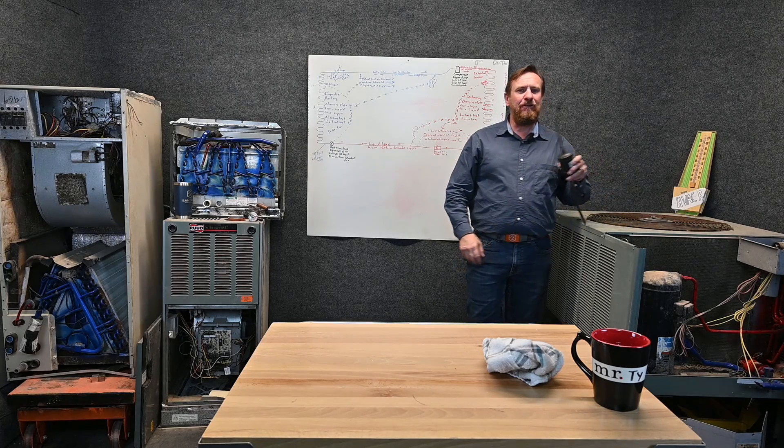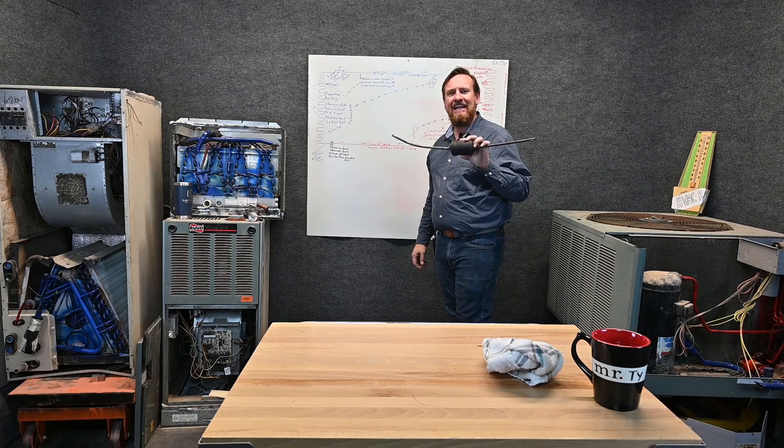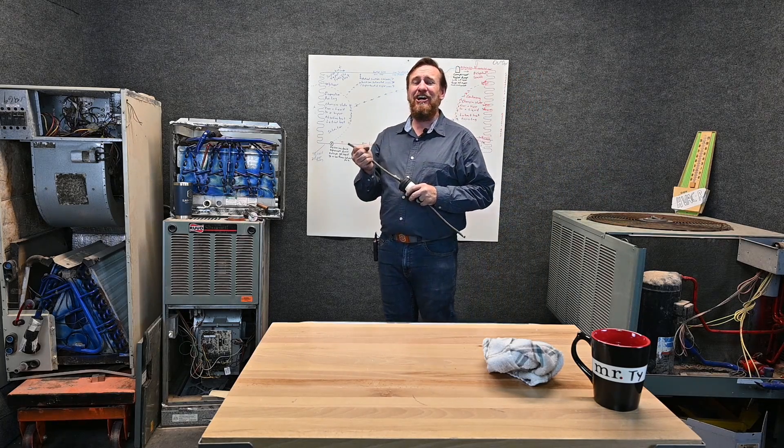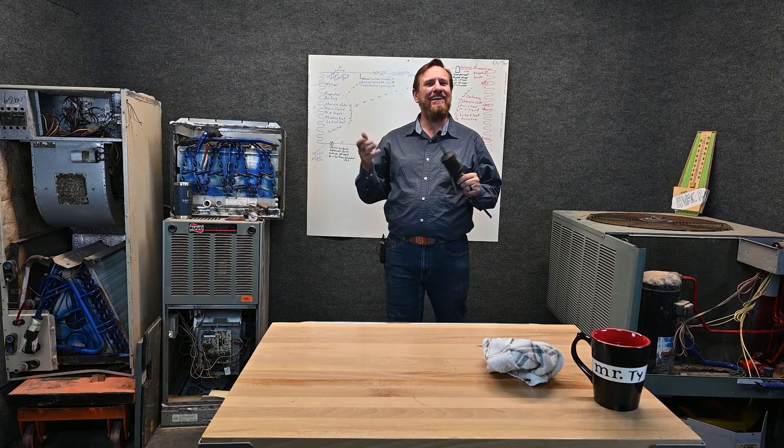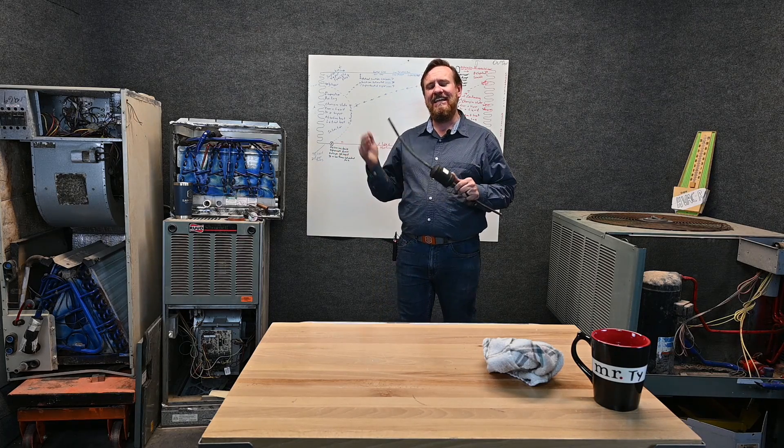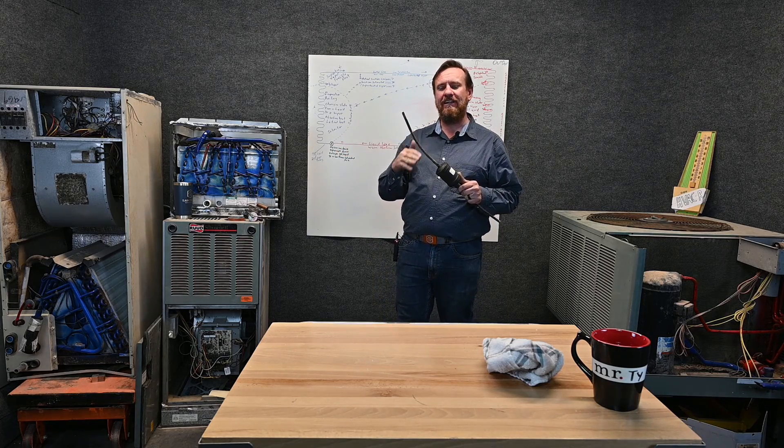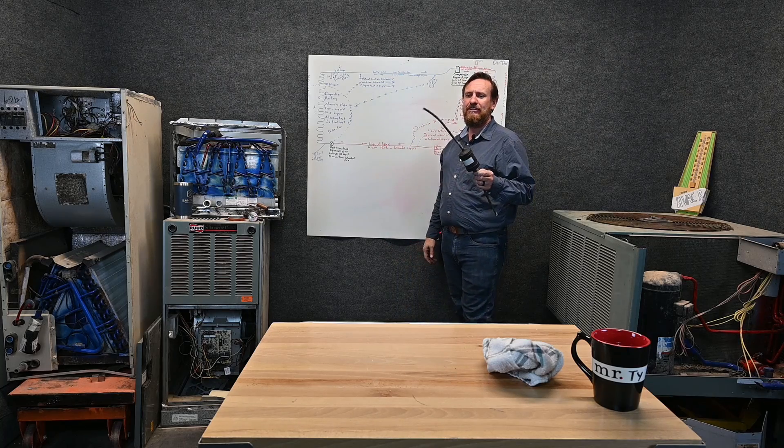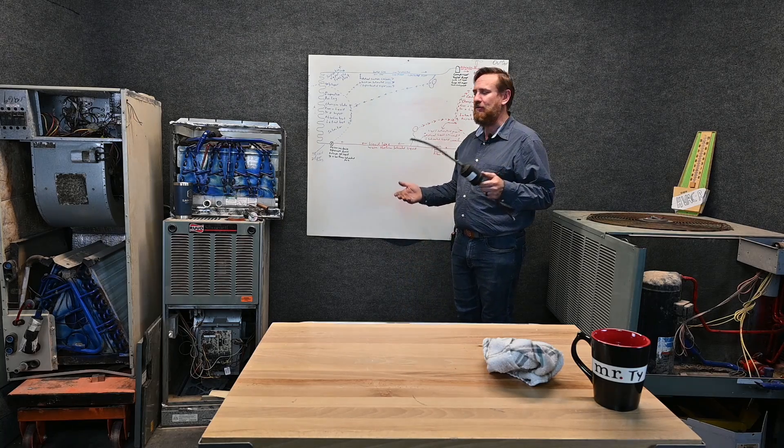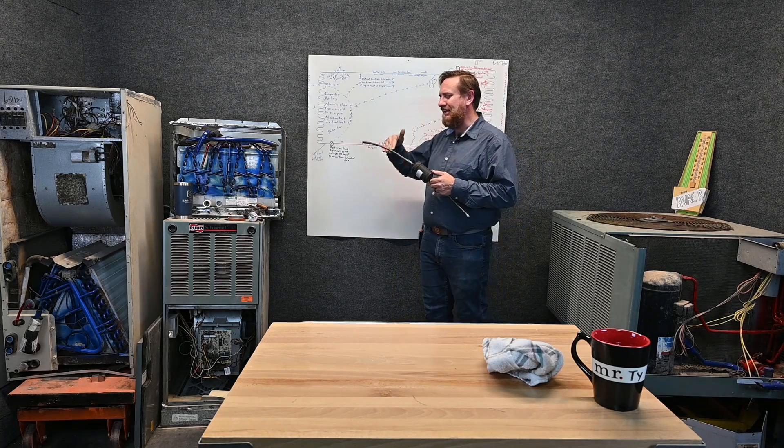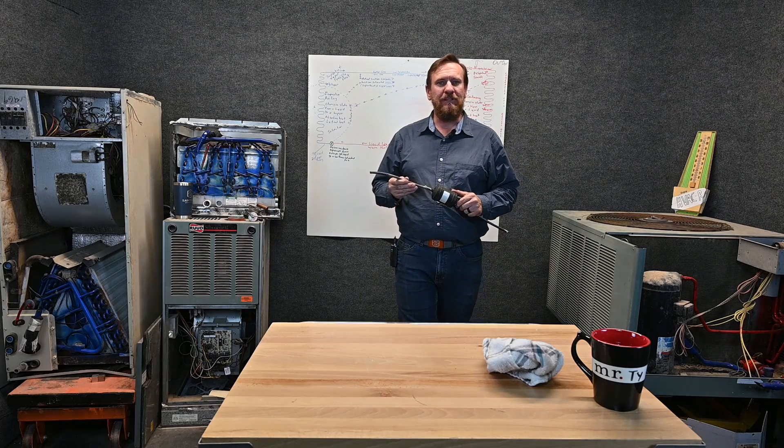But let's say our liquid line runs up the wall then it runs across the attic and our attic is say 110 degrees Fahrenheit. Second law of thermodynamics states the heat will go to the cooler area. So if this line temperature was 95, the heat from the attic is going into this line. We are losing subcooling.